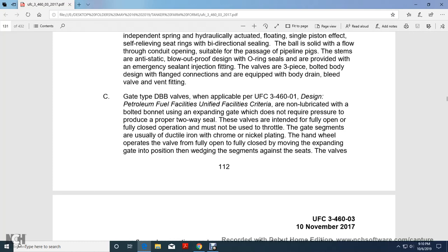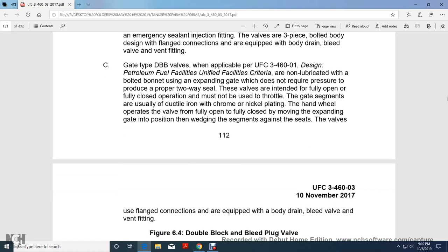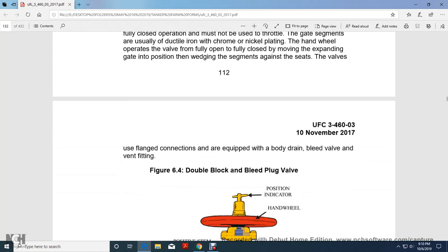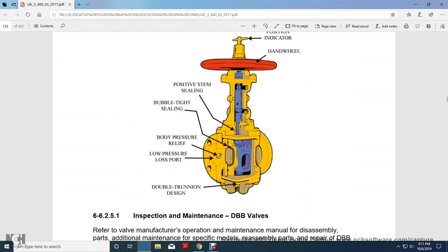The gate segments are usually ductile iron, chrome, or nickel plated. The hand wheel operates the valve fully open or fully closed, moving the expanding gate position, wedging the segments against the seats. The valves using flange connections are equipped with the body drain and bleed valve with the vent and fitting of the double block and bleed valve shown in this.